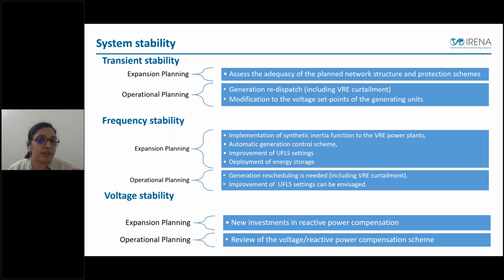Moving forward, the same analysis applies for system stability studies. In case of transient stability, under expansion planning, the guide would recommend that it is necessary to assess the adequacy of the planned network structure, whereas under operational planning, generation redispatch, VRE curtailment and modification of voltage set points of the generating units can be done. For frequency stability, which is of great importance to most system operators, expansion planning would recommend measures that might include synthetic inertia function for VRE power plants, automatic generation control scheme, improving UFLS settings and deployment of energy storage. But in case of operational planning, it would be generation redispatch and improvement of under frequency load shedding settings.